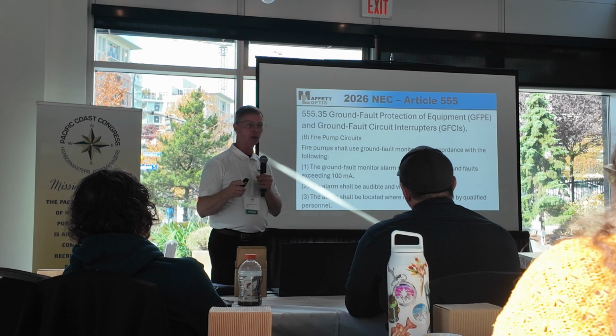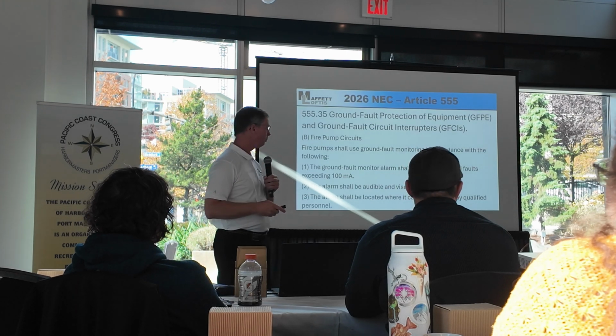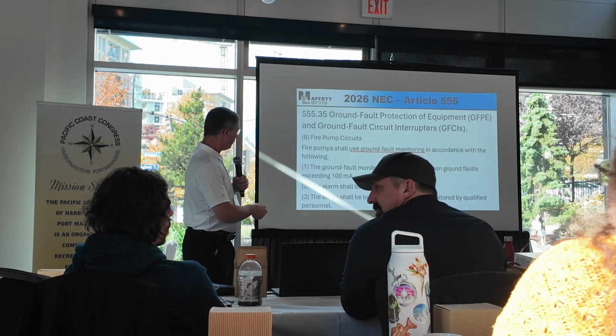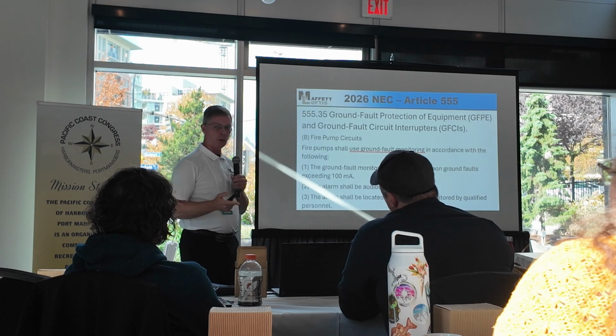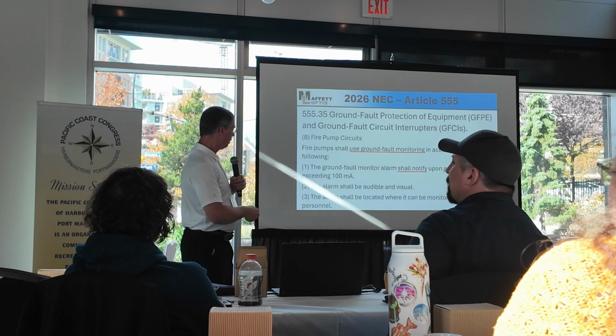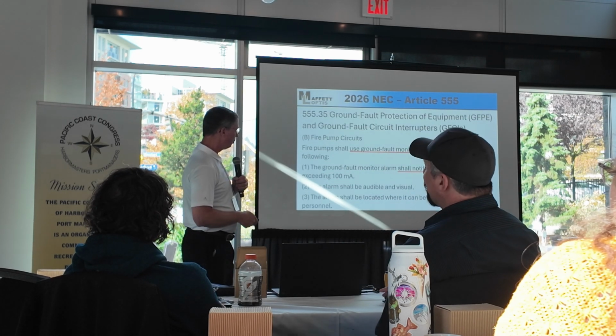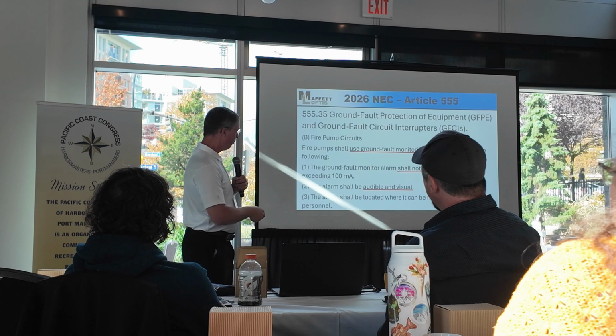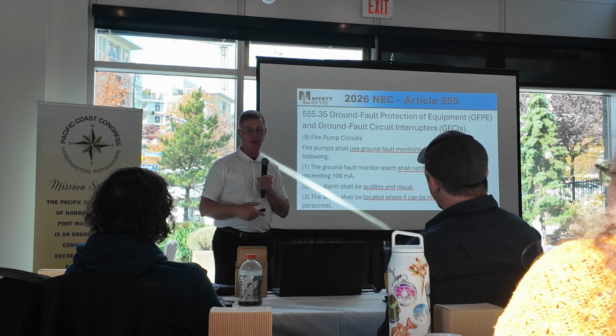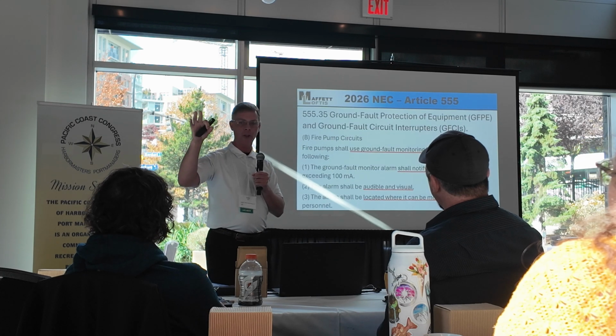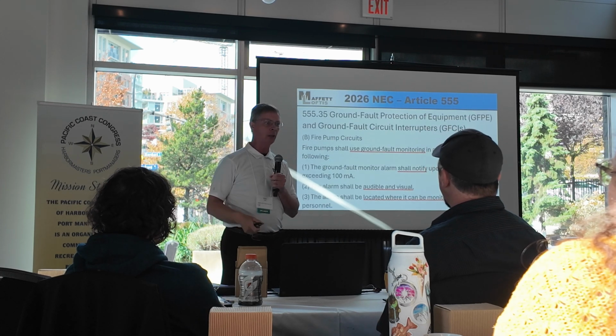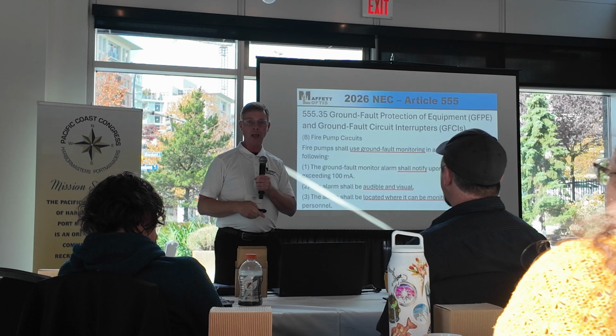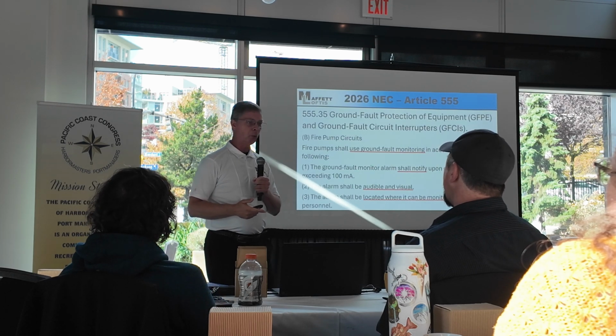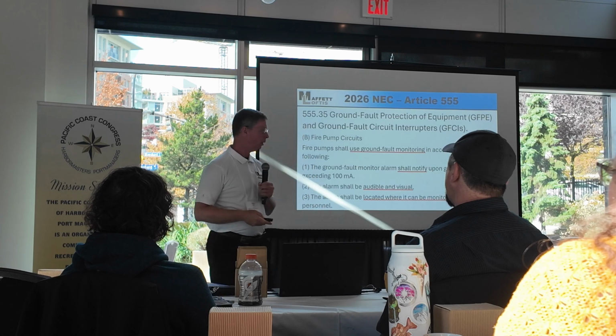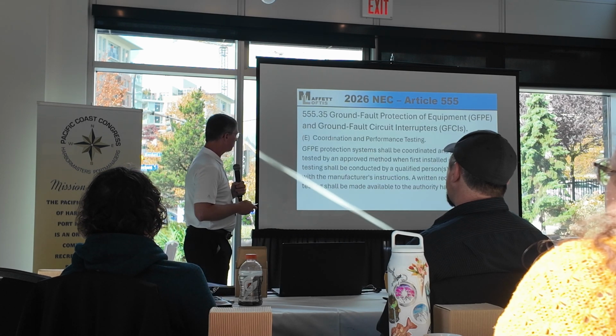And there's a difference. Ground fault monitoring is that we're monitoring for leakage currents. We're going to monitor for leakage currents, but we're not going to trip the power. Okay? But the ground fault monitor shall notify and have an audible and visible alarm that's located where it can be monitored by qualified personnel. That can be in a ship store, it can be on the dock with an audible and visible horn that just sounds that, hey, this fire pump circuit's leaking 100 milliamps. They go repair it. But we're not going to shut it down. So that's another piece that got put in there.